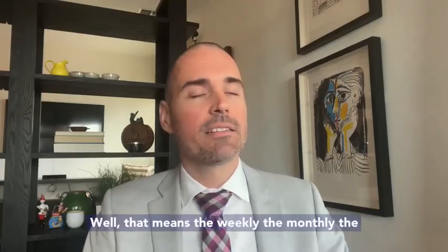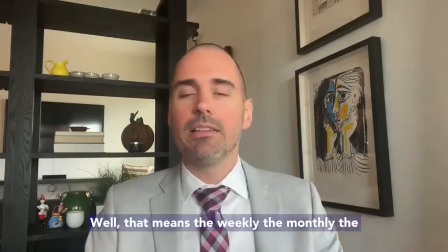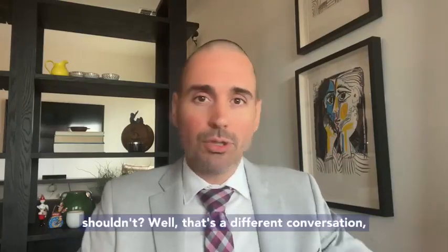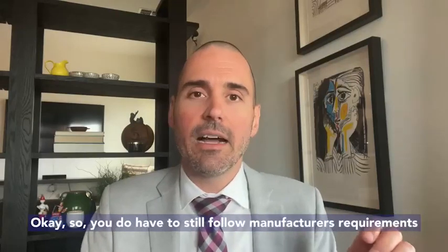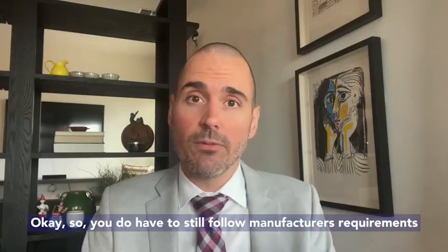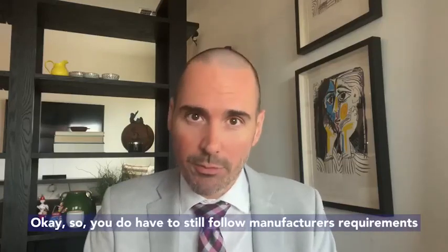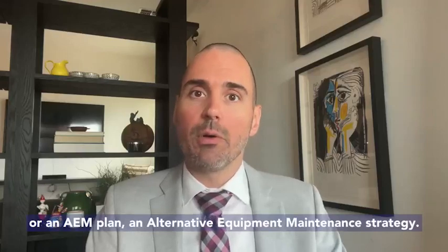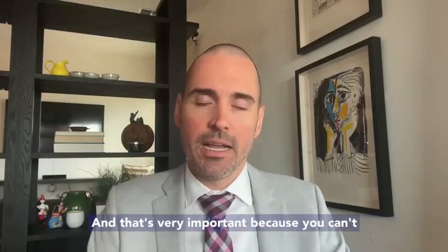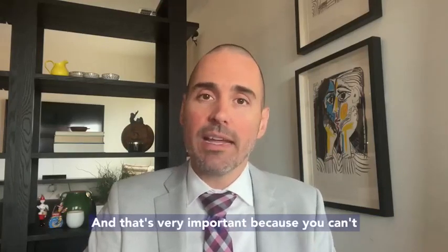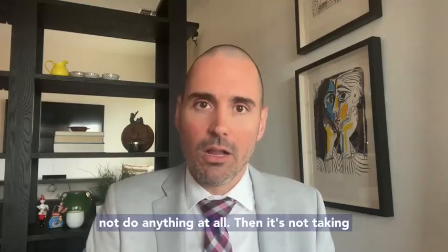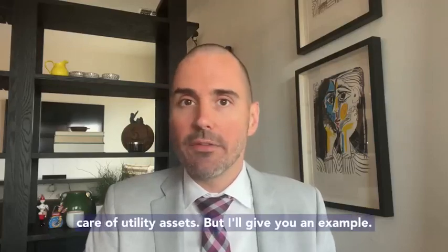That means the weekly, the monthly, and so on and so forth. But does that mean that you shouldn't? Well, that's a different conversation, okay? You do still have to follow manufacturer's requirements or an AEM plan, an alternative equipment maintenance strategy. And that's very important because you can't just have the generator and not do anything at all. Then it's not taking care of your utility assets.